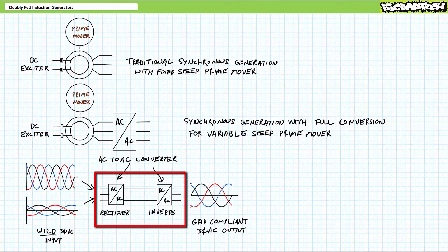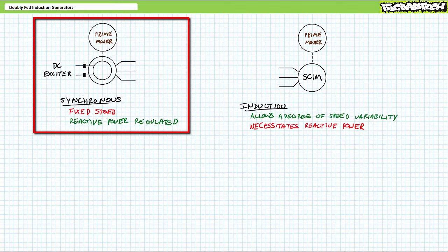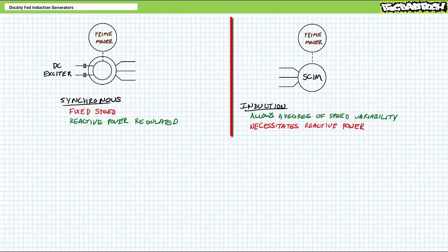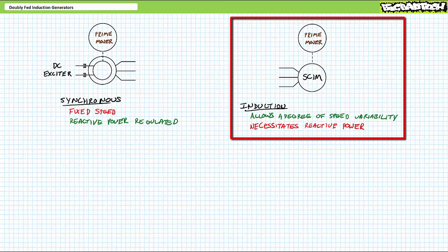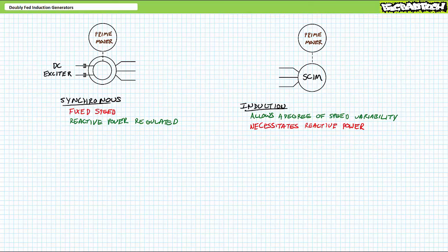We've essentially got two choices, each with desirable benefits and undesirable drawbacks. First, synchronous generators, which do allow for a fine degree of control over reactive power, but need to be driven at a fixed speed. And second, induction generators, which do allow a degree of speed variability, however, necessitate the constant consumption of reactive power.